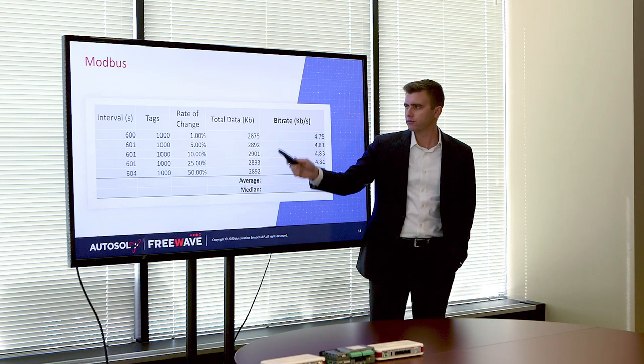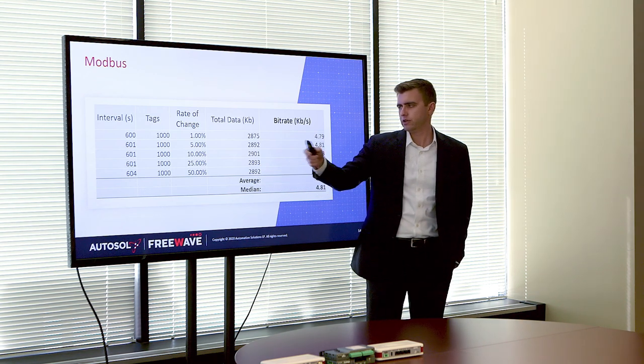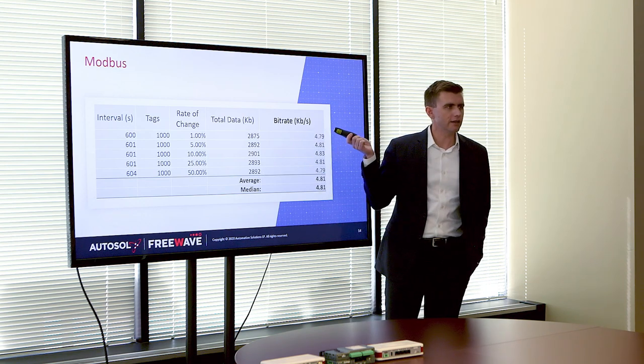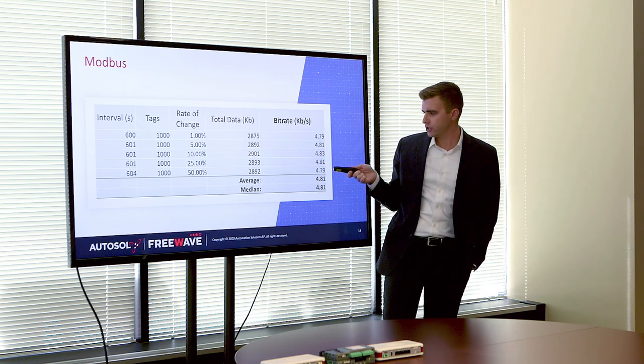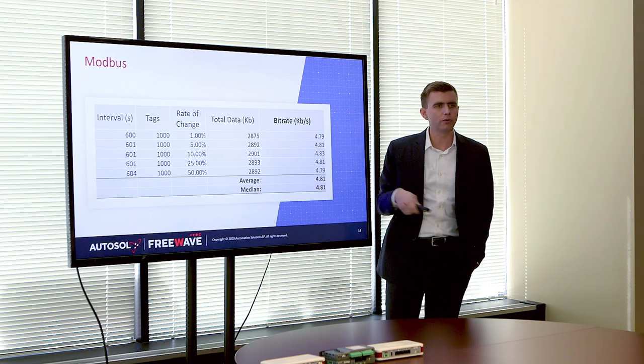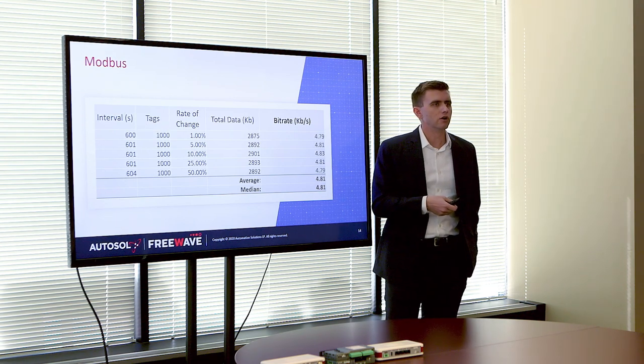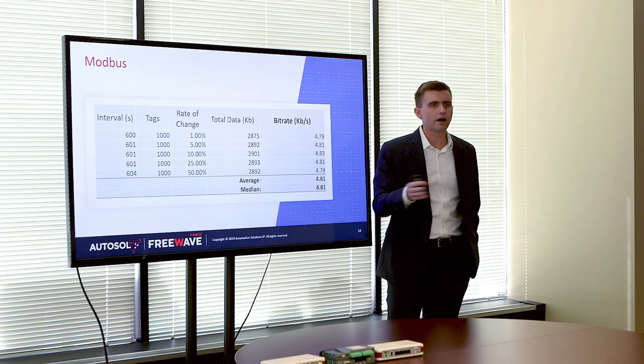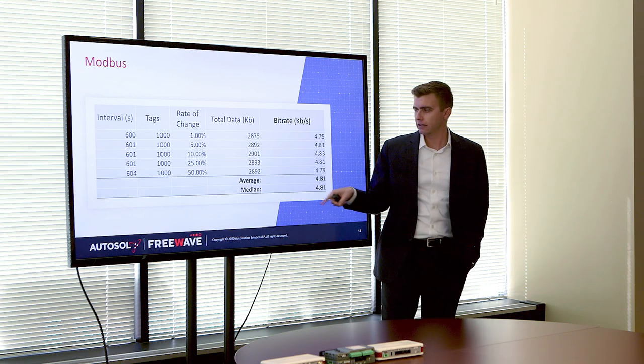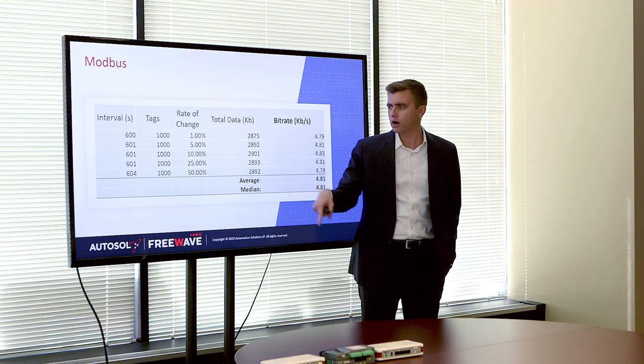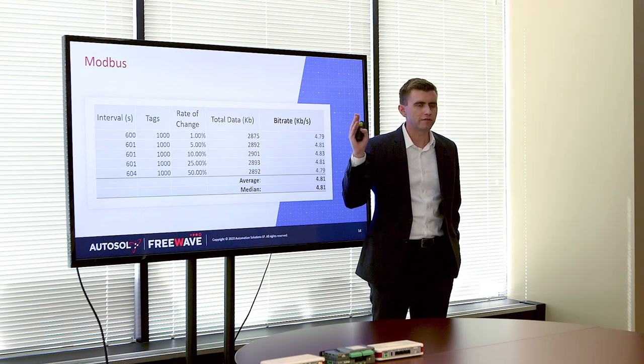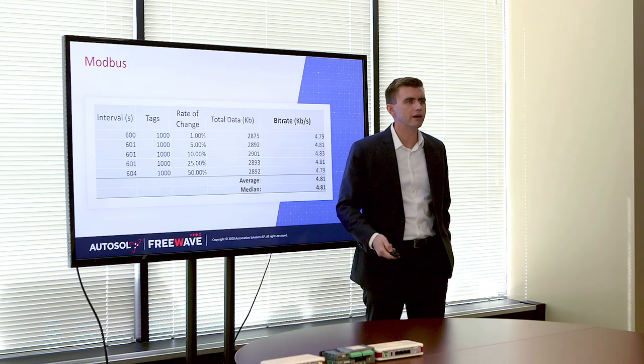2,875 kilobytes for 1% change rate, 2,892 for 50% — very little difference. Breaking that down to kilobits per second, you get an average and median of 4.81 for each one. Since the average and median are the same, there's no outlier skewing results. Basically, no matter what the rate of change was, we used the same amount of bandwidth, because in poll-response we have to send every value that was requested up every time.